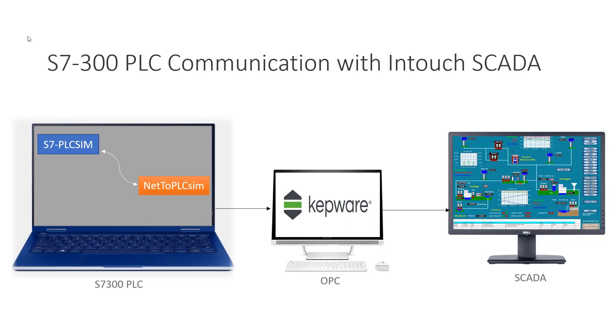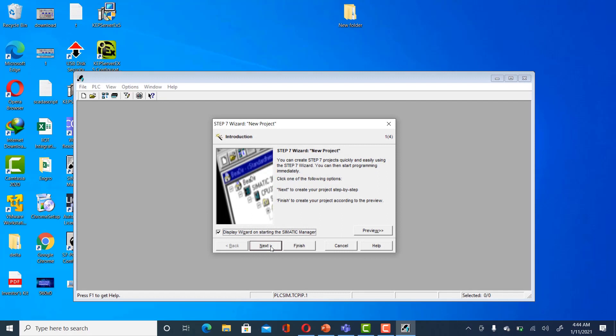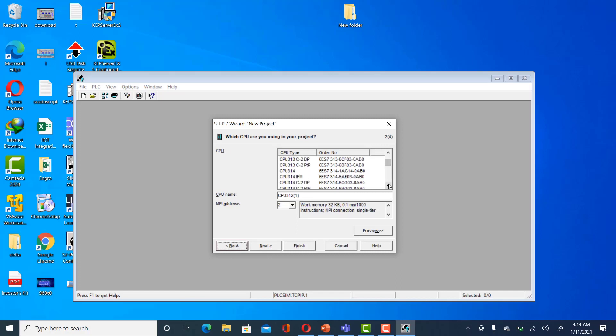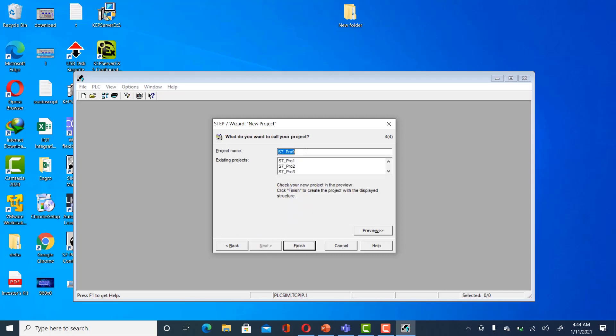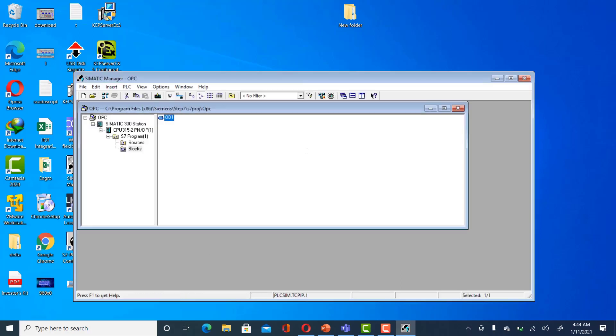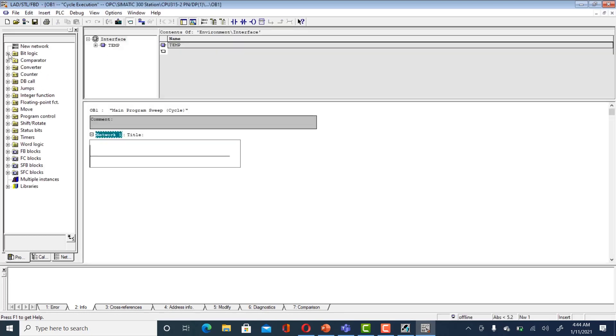From Net2PLCSim you get data on the OPC server. First, open up Simatic Manager software. When selecting a CPU, always choose a PN-type CPU that supports PROFINET, which is Siemens' Ethernet protocol. Click next, select the ladder, click next. You can create a project name such as 'OPC'. We are creating a small project with one analog and one digital signal to extract those tags on OPC.